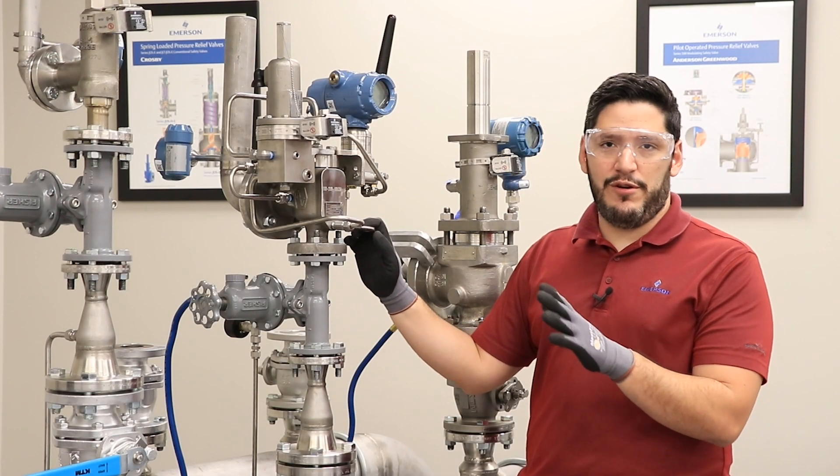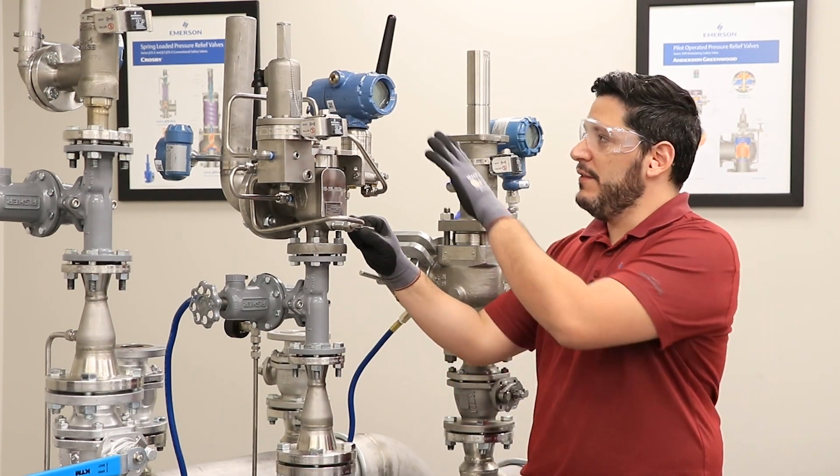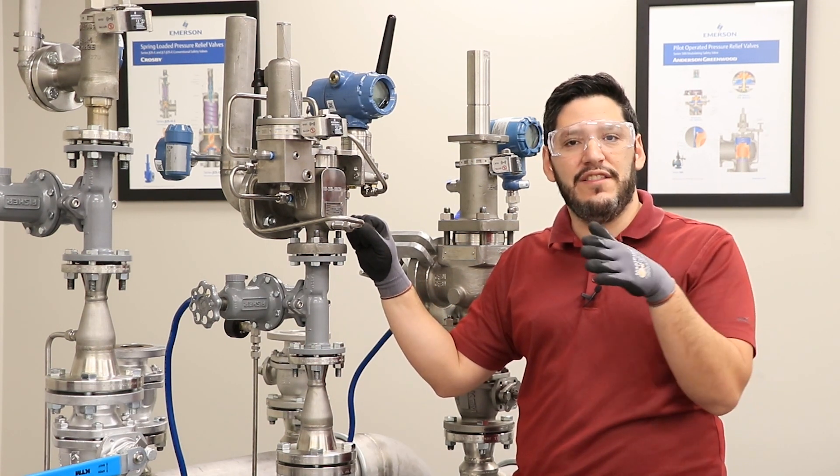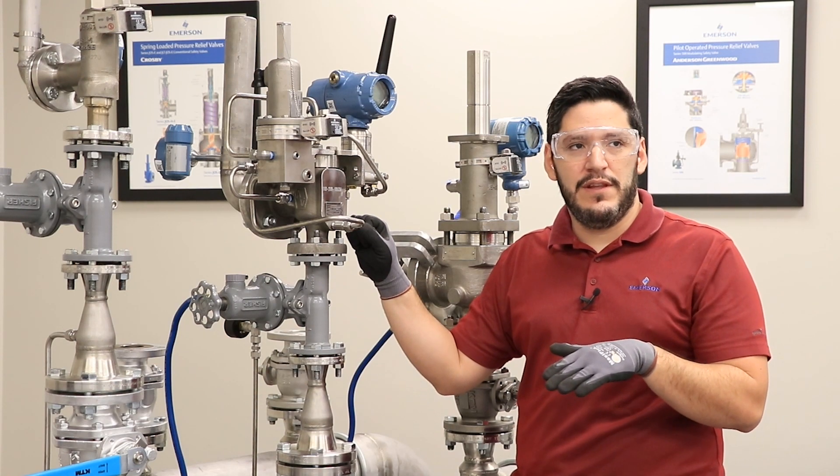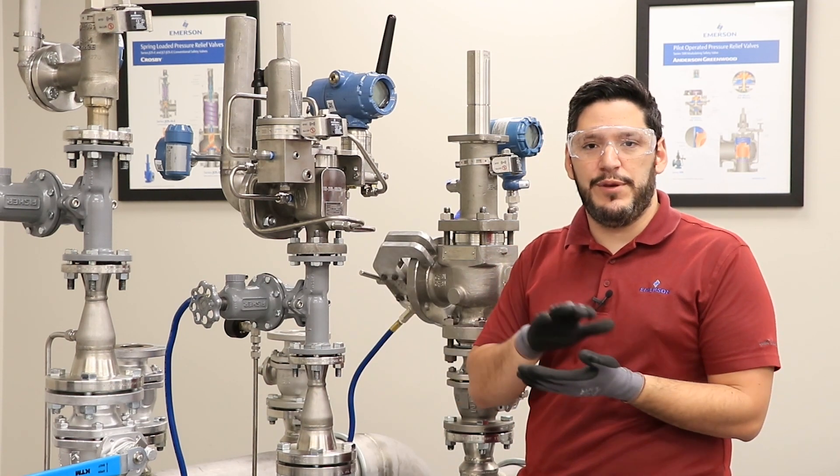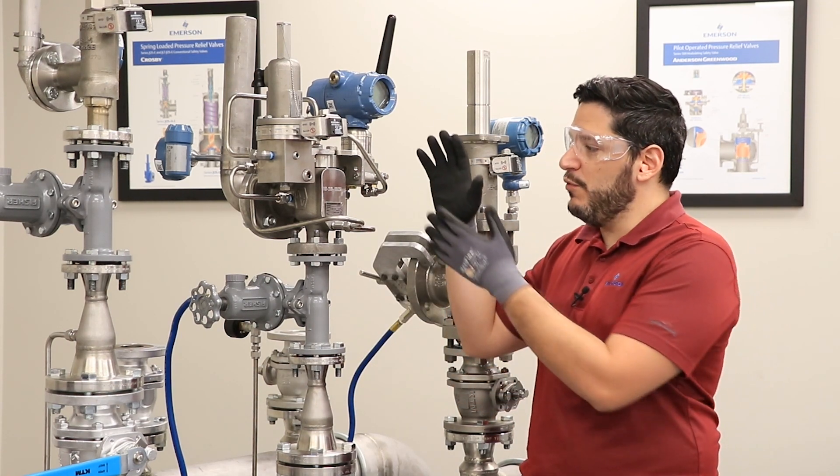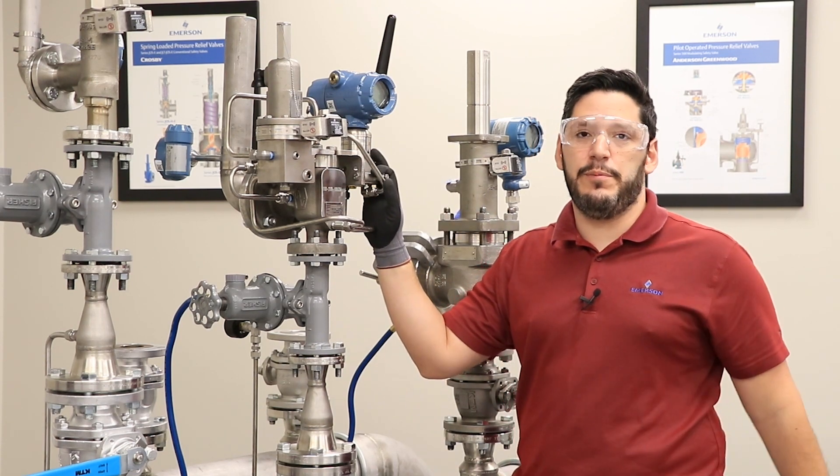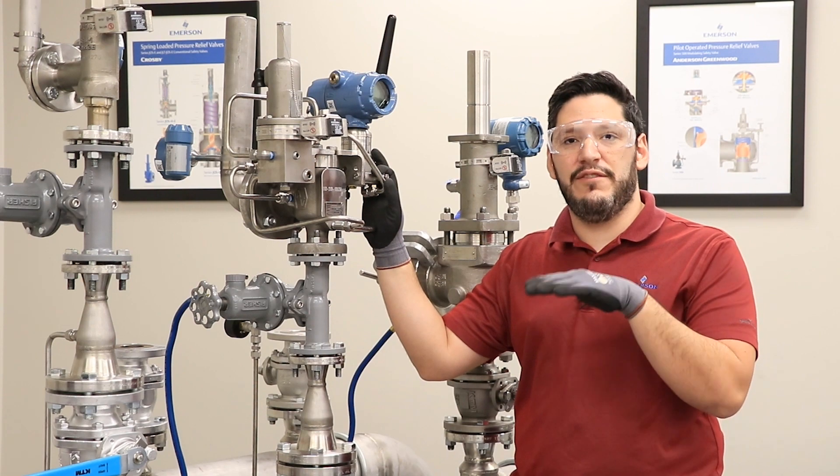As you can see from the graph we just saw, the differential pressure gets correlated to that valve percent lift as we track the lift over time. Having this information can help you quantify what was really happening at the outlet of the PRV when your PRV was open. So you can quantify the flow through that valve.